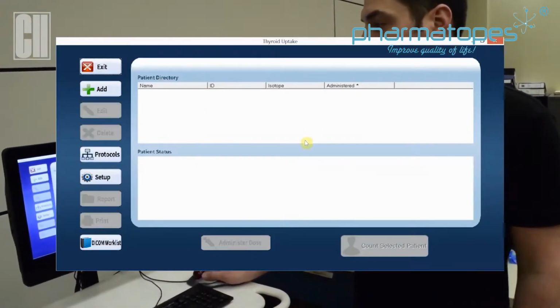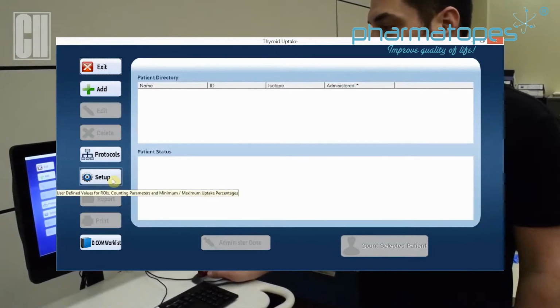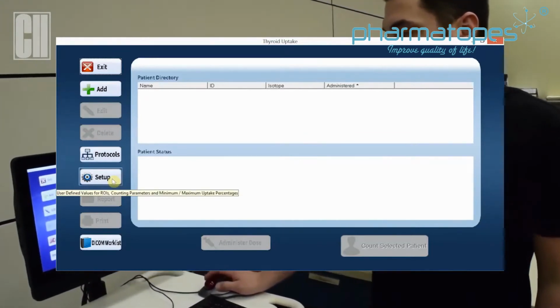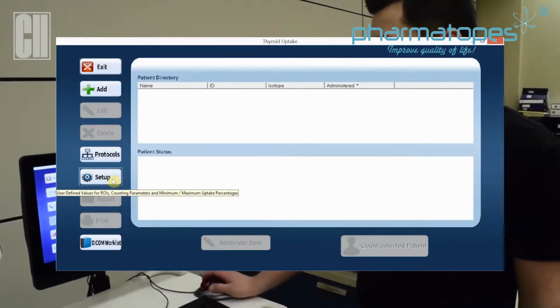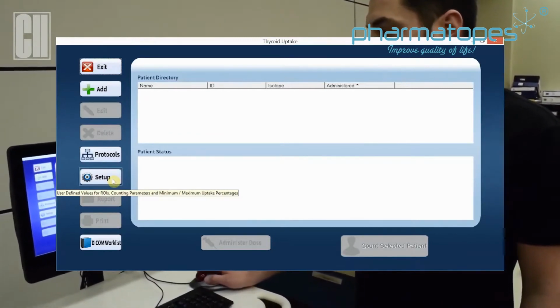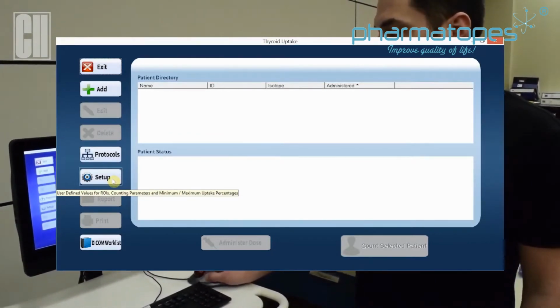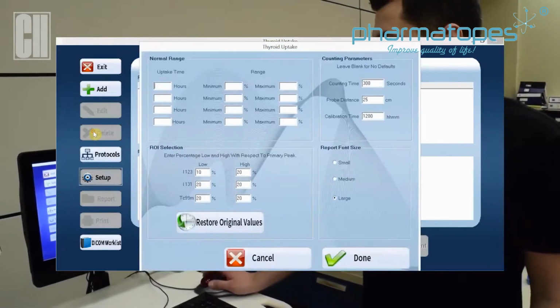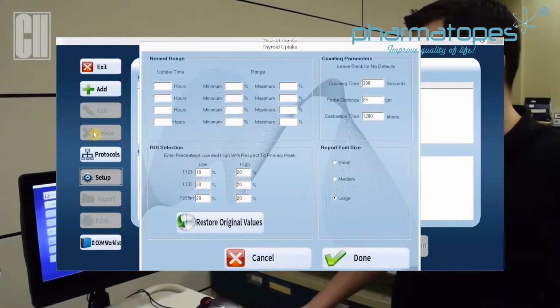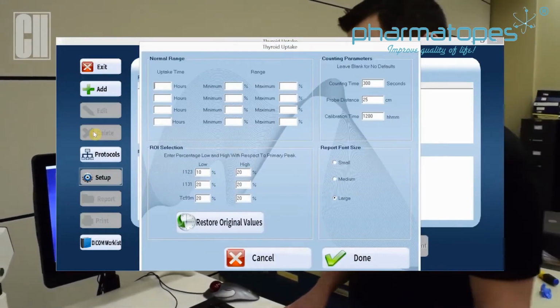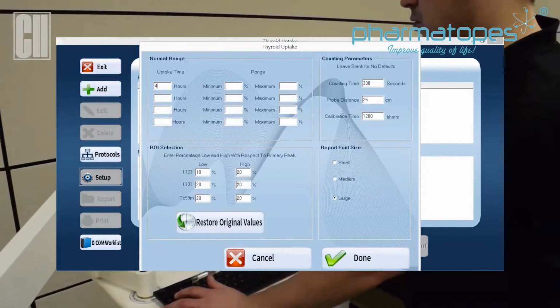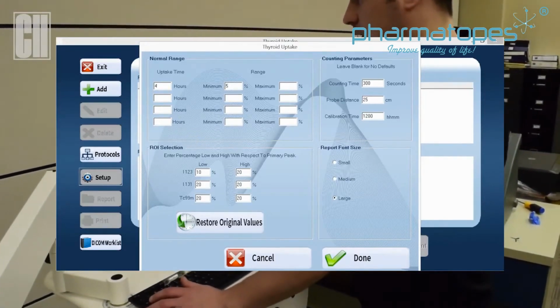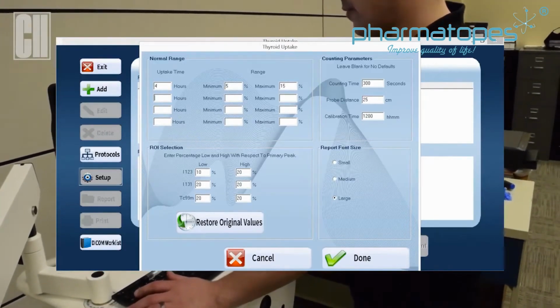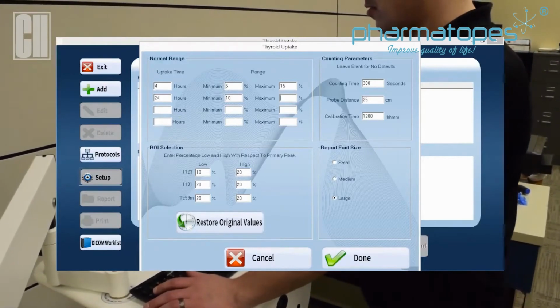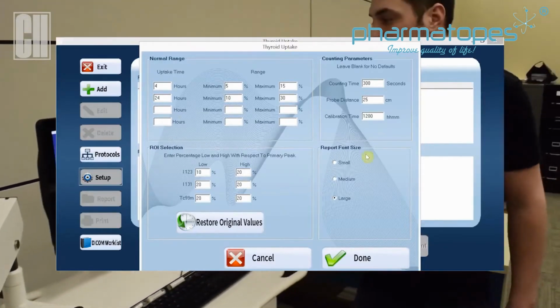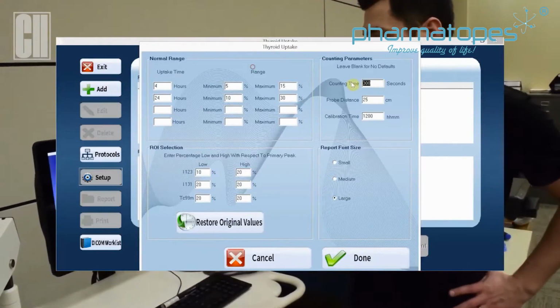So in the thyroid uptake screen, we've already added a protocol, which is still in there from the initial setup. We're now going to do a general setup for the study. Here is where we're going to enter the normal ranges for your typical uptakes. An example, for a 4-hour uptake, we might see 5 to 15%, and for a 24, we might see 10 to 30%. Counting time can be set by the facility.